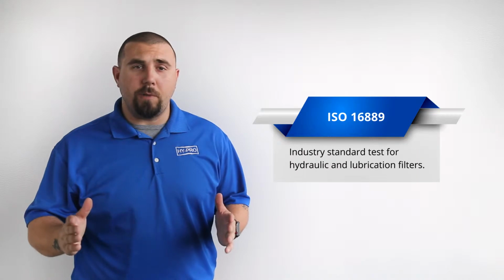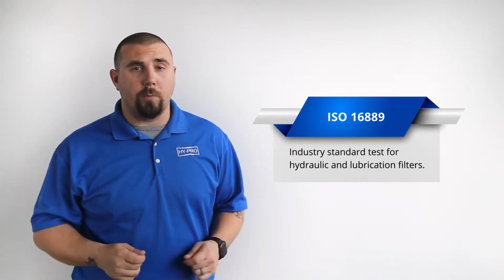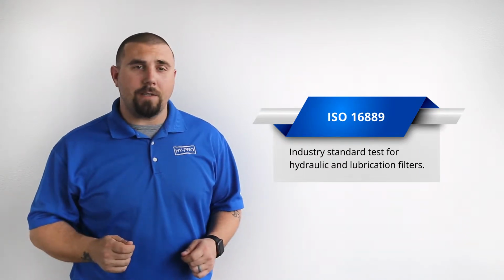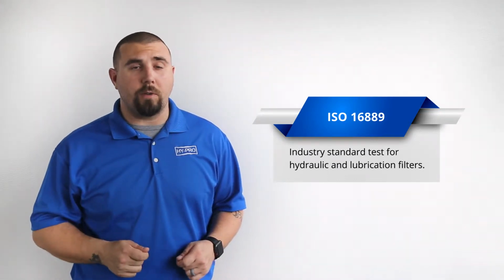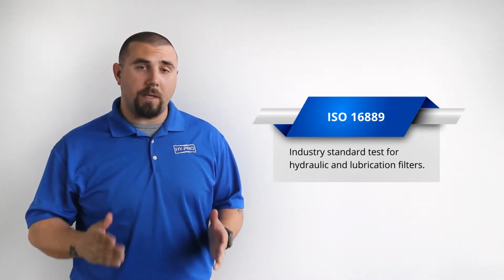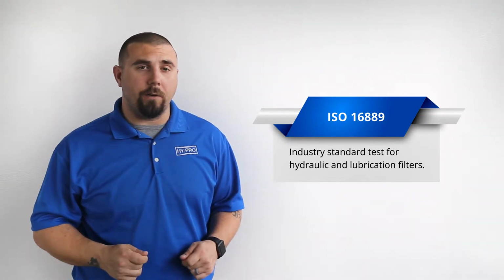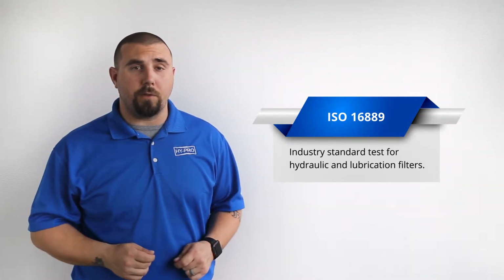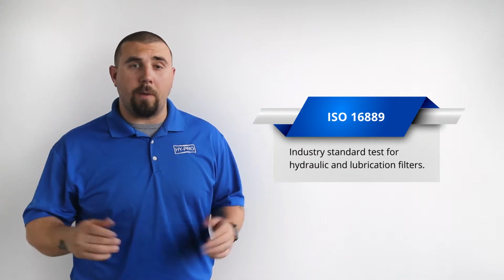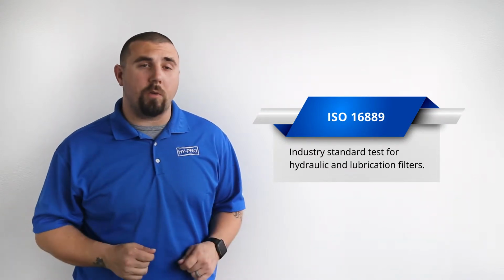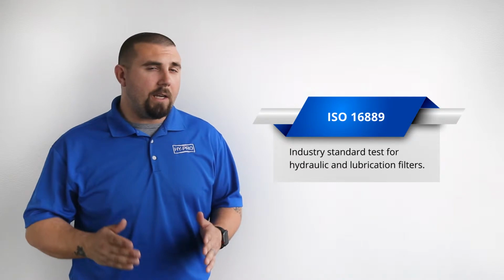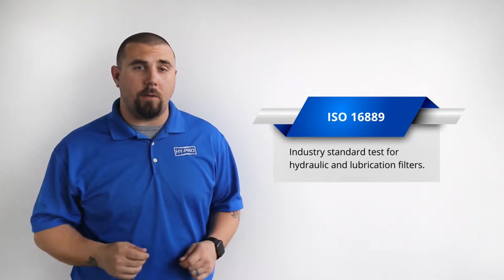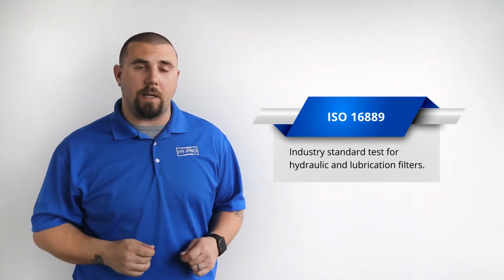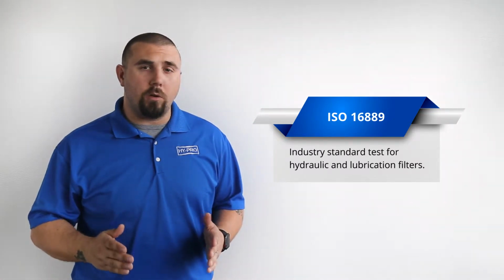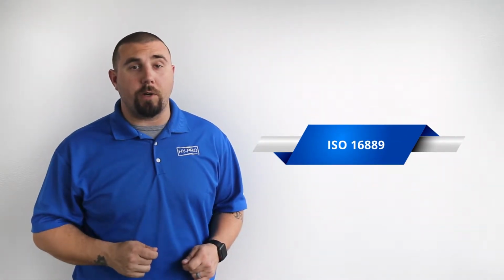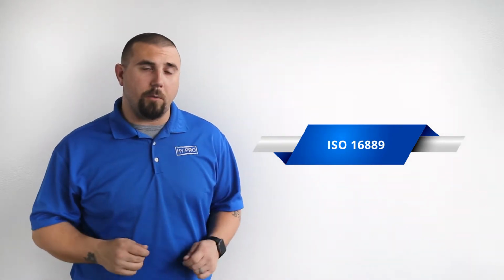A steady flow rate must be chosen by the operator and measured in liters per minute. ISO medium test dust must be used in one of 3 gravimetric level conditions, either 3 mg, 10 mg, or 15 mg per liter, and continuously injected into the filter test system reservoir. There must be automatic particle counters calibrated in accordance with ISO 11171 in use upstream and downstream of the test element, with counts being taken every 60 seconds throughout testing. Testing will conclude once the test filter's terminal differential pressure has been met. All results must be recorded.